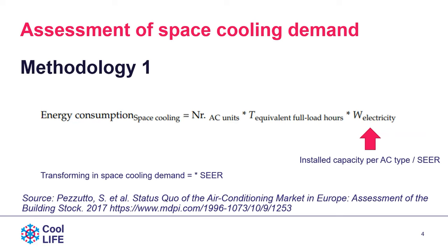One way to assess space cooling demand is to pass through the space cooling consumption, taking into account the amount of air conditioners per type in a certain area, for example a country. Then take into consideration the equivalent full load hours and the work input. The work input is given through the installed capacity per air conditioning type divided by the energy efficiency indicator, in this case the seasonal energy efficiency ratio.